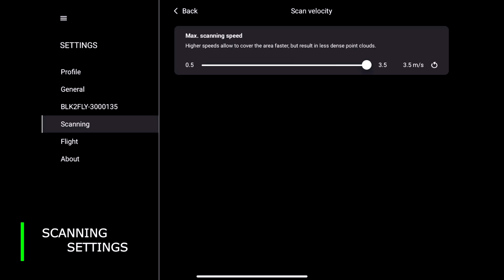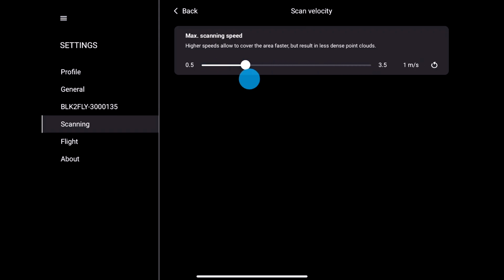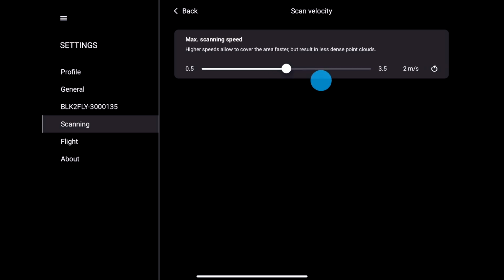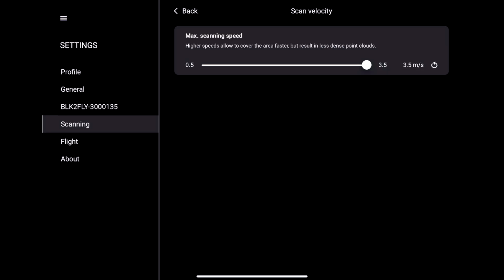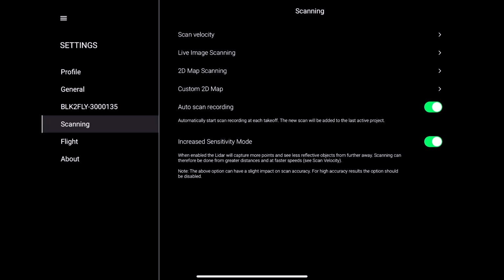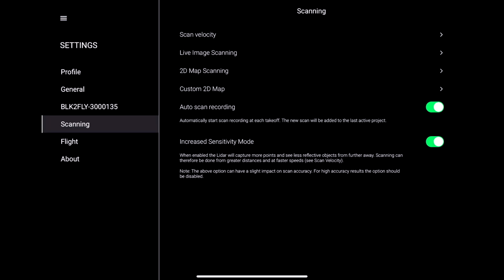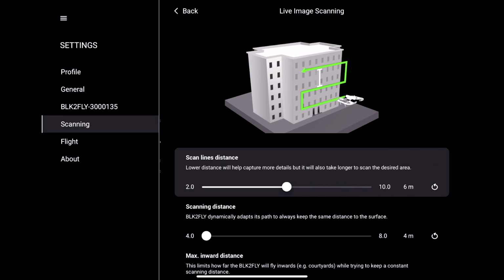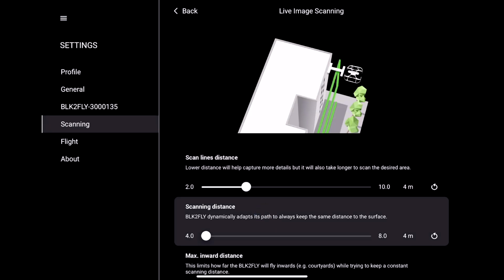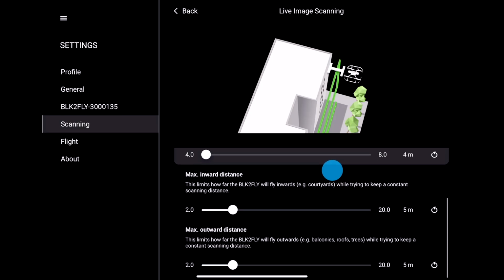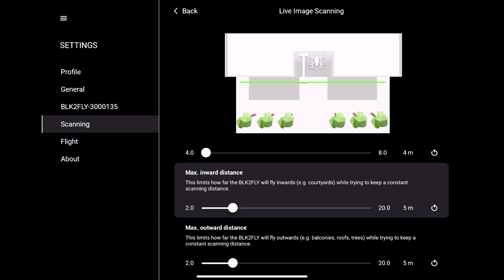Now, let's check the scanning settings. Scan velocity. The maximum scanning speed settings define the target speed of the scanner for all autonomous scanning modes. It can be set anywhere between 0.5 and 3.5 meters per second. However, the optimal scanning speed to achieve the best point cloud quality is 2 meters per second. Now let's set up the parameters for live image missions. We recommend to keep the scan line distance somewhere between 4 and 6 meters, and keeping the minimal possible distance to the object of interest, which is 4 meters. Max inward and outward distances can be also set here. This time we will keep it at 5 meters.